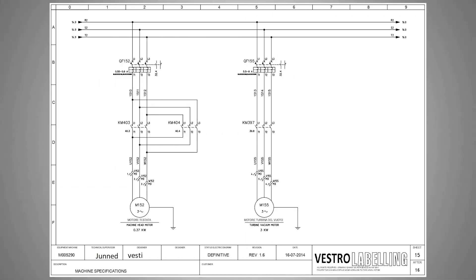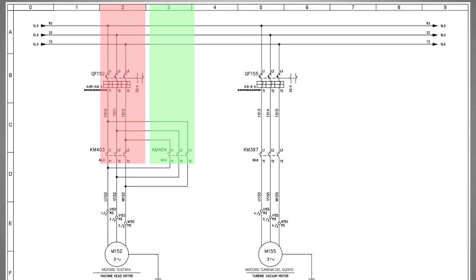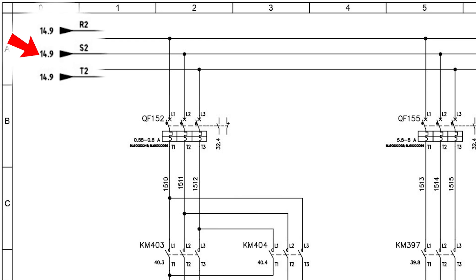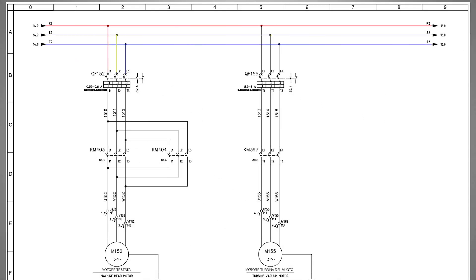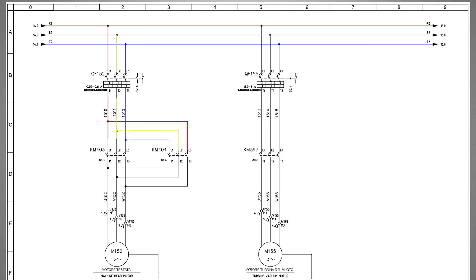On page number 15 we can find these normally open contacts in column number 2 and column number 3. The three-phase supply coming from page number 14 is fed into the motor protector breaker QF152. The output three-phase supply from the breaker is connected at the input terminals of contactors KM403 and KM404. L1 and L3 wires are interchanged at the input side of one contactor to run the three-phase motor in reverse and forward direction.